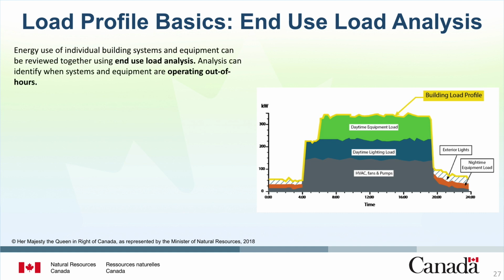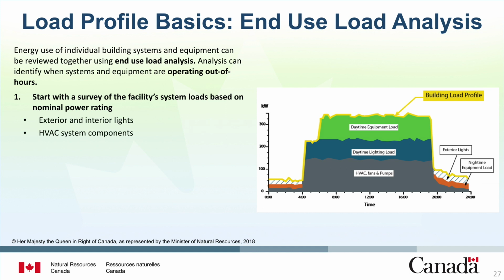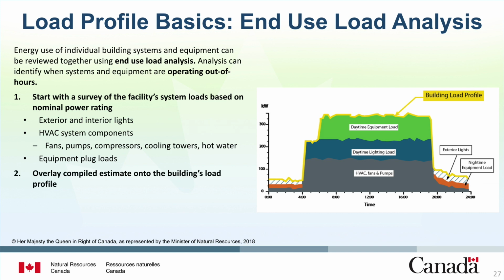The energy use of individual building systems and equipment can be reviewed together using end-use load analysis. This type of analysis can identify systems and equipment that are operating out of hours and lead to reductions in a building's overall base load. To perform an end-use load analysis when submetering data is not available, start with a survey of the facility's system loads. The survey should include the nominal power ratings of equipment, including exterior lights, interior lights, HVAC system components such as fans, pumps, compressors, and cooling towers, hot water, and plug loads from equipment such as computers, copiers, and printers. Once this information has been gathered, overlay the compiled estimate for each end use onto a building's load profile.